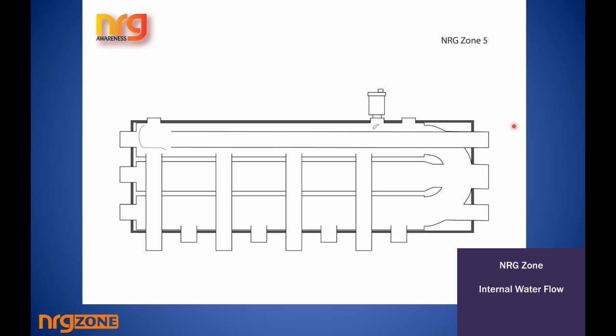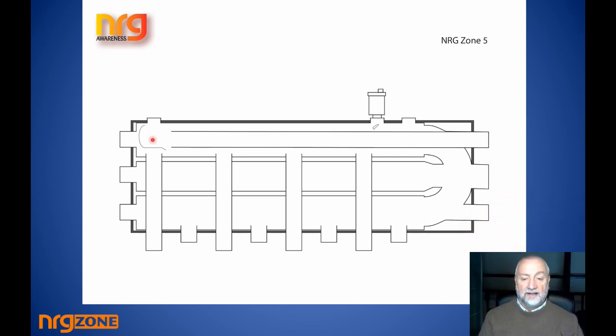left hand side. You could also of course have a boiler come in on the right hand side, flow through this pipe that traverses the unit, hits the center of this V-shaped baffle, turns back on itself, and as it travels back goes again over the bypass and can go back to where it came from. But you can also bring a flow in, say top right hand corner, travel left to right across the baffle, having left the pipe, and down, and then go to the bottom left hand corner. And also just the same, it can go in the top left hand corner, travel across the top chamber, the flow chamber, down through the 100% open bypass, and back at the right hand side. So it's extremely versatile for piping connections. You can actually do more than that, but we're just talking about the starting basics, let's say.